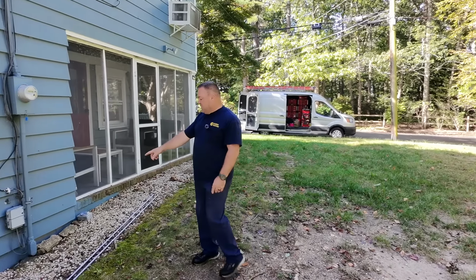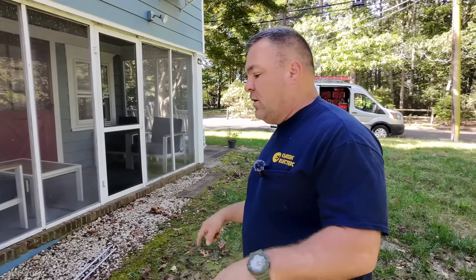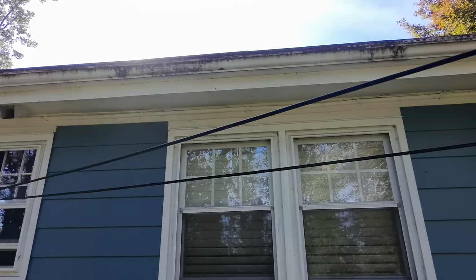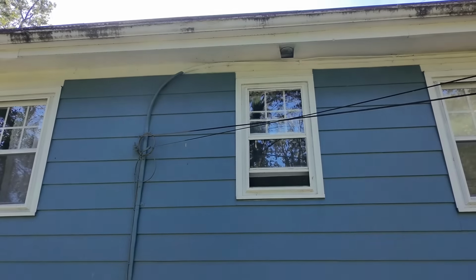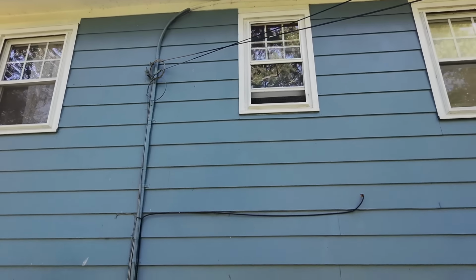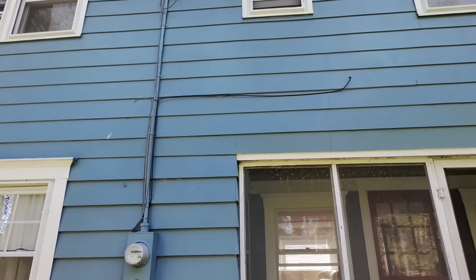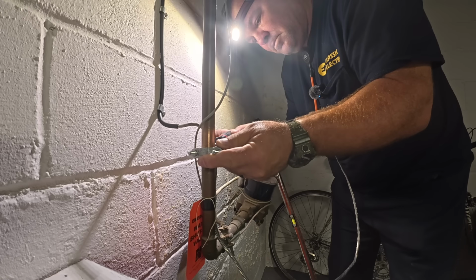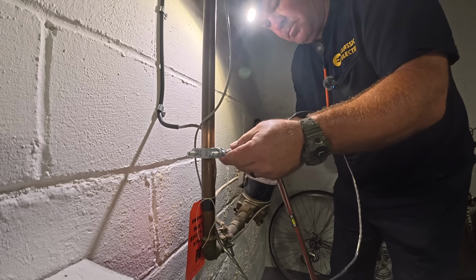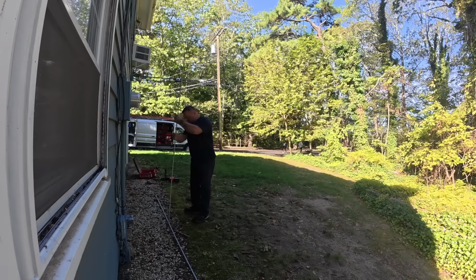So what we're gonna do today is drive a couple ground rods, and once they're driven, we'll run our grounding electrode conductor. We're going to be replacing the 200 amp riser all the way up to where it is here underneath that soffit. This job should be pretty cut and dry. We're also gonna run the water ground over to the water main.